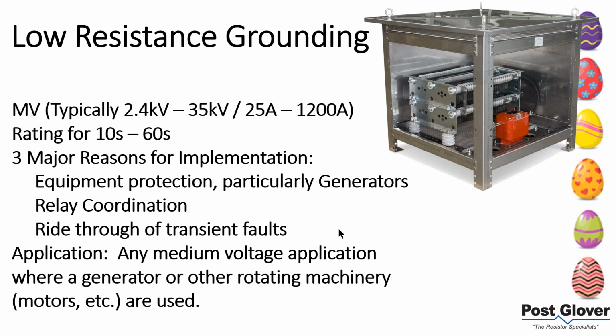Typical ratings for low resistance ground are 10 to 60 seconds, with 10 seconds being most common. You're essentially going to be tripping on a ground fault. You're going to segregate that portion of the system, and then you're going to go offline. But there are several reasons why we use low resistance ground. One is for equipment protection. You're going to be lowering the amount of current that flows, especially compared to the effective or solid ground systems. Comparatively to that, generators, they're often used for generator protection.